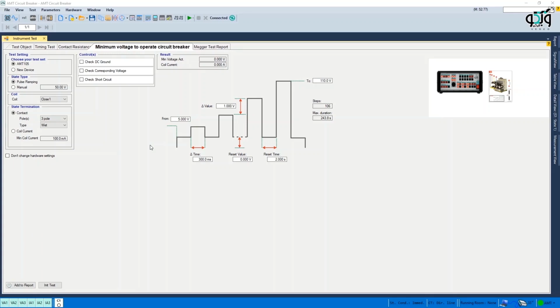Circuit breaker operation minimum voltage test. One of the most important tests that can be performed on circuit breakers is the circuit breaker operation minimum voltage test, or minimum voltage, which is performed in minimum voltage to operate circuit breaker tab. In this test, it is possible to find a minimum voltage which can cause the circuit breaker to operate by gradually increasing the voltage applied to the two ends of open or closed bobbin.